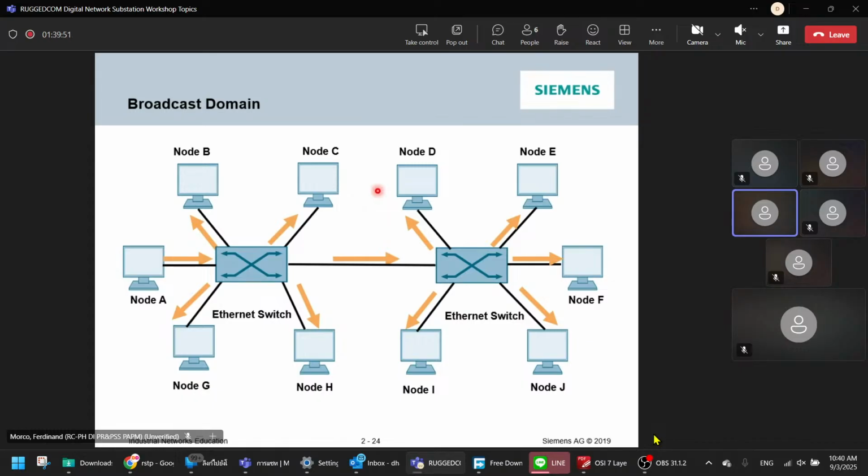Because I compare with the other competitors, right? It will have the priority for GOOSE and SV. It will detect by protocol, not detect by port. What do you think about that? Yeah. Now, if you are using VLANs or tagging, you can create VLANs without priority. But depending on your tools, you can create VLANs with priority, or you can set it up with priority. This one you can create by default. This port has its priority. It's 1 or 0. You can change it.